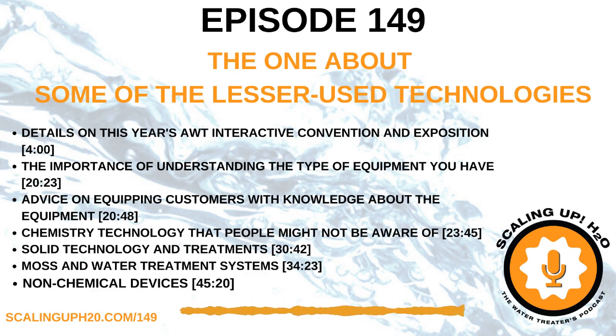One of the ways I love to explain film forming technology is: imagine a tadpole with a big mouth on the end, and this tadpole loves to bite into surfaces of metal. If it's biting into a chunk of rust, it's going to bite on that rust and hold on, and you've got this tail out on the end. As the water passes, it puts pressure and pulls on the tail, and because that rust is weak, it just pulls it off. Then another film forming amine is going to bite into the section right next to it. Or if there's scale—because a lot of people don't realize calcium is a metal—you're going to bite into the calcium and pull that off as well. So it's going to clean up your system.